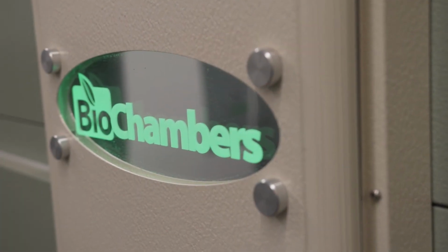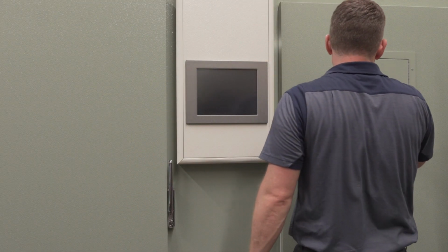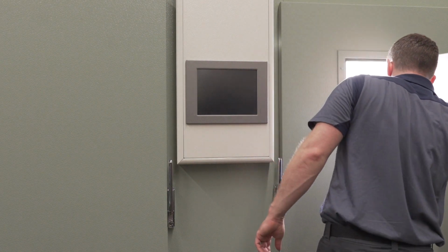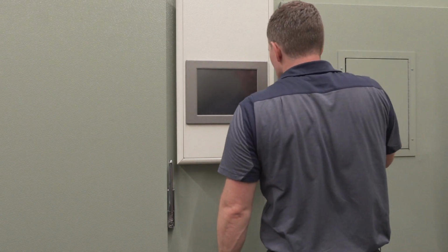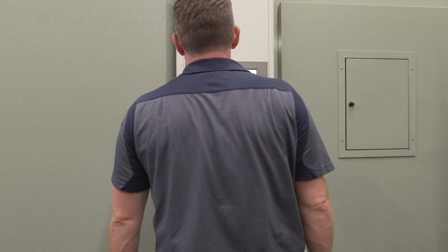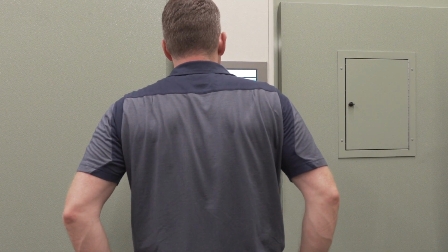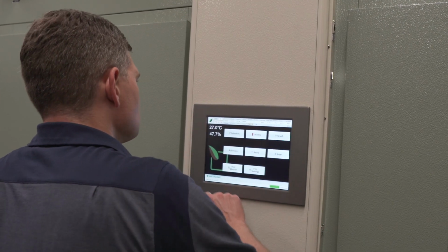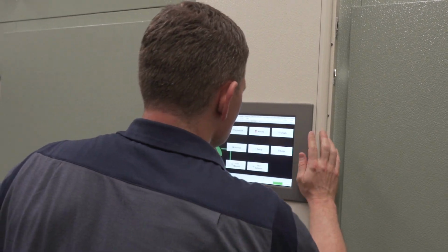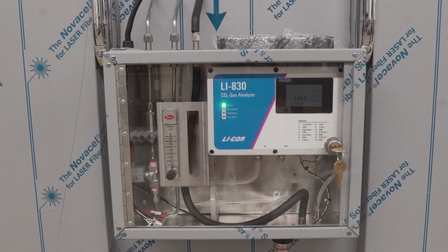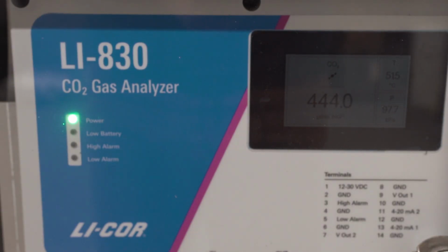Every day that you're using a growth chamber, you should check that it's running with the green light on, either on the chamber itself or connected with VNet. It's also good daily practice to check that all the lights are on as scheduled and that the chamber air temperature matches the set point. If humidity or CO2 control is installed, also check that the actual chamber values are close to the set point.